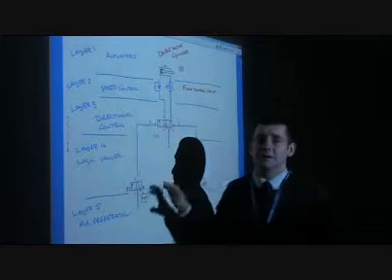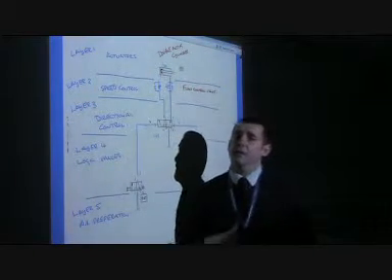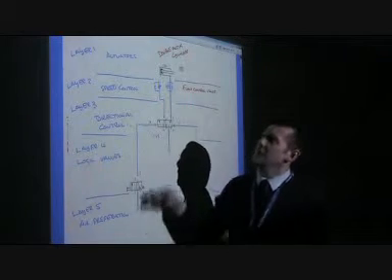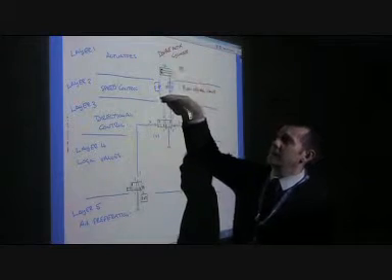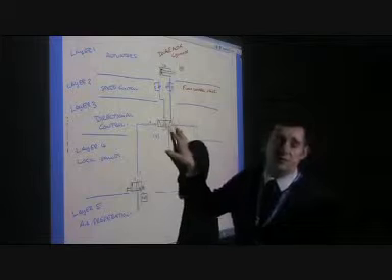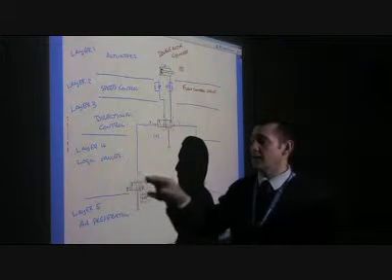There is an international drawn standard for fluid power circuit diagrams. That drawn standard is ISO 1219. It stipulates that we have to use 5 separate layers for the drawings. Layer 1, our actuators sit in. Anything for speed control is in layer 2. Directional controls such as 5-2 valves sit in layer 3. The logic valves that govern the sequence the circuit operates sit in layer 4, and any air preparation sits in layer 5.